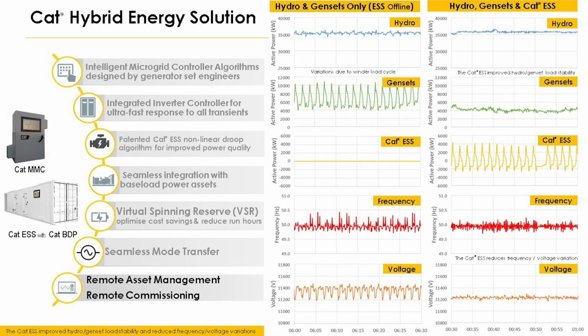The gensets were, of course, swinging very dramatically to deal with the winder load. They've been smoothed out quite considerably as well. You'll notice there are still some gensets on, but this was because the hydro was only at around the 35 megawatt mark at this particular point. The energy storage system is, of course, now accepting a lot of the swinging loads which previously were sitting on the gensets, and the frequency and voltage have been smoothed out quite dramatically, as you'll see from the lower two illustrations there.